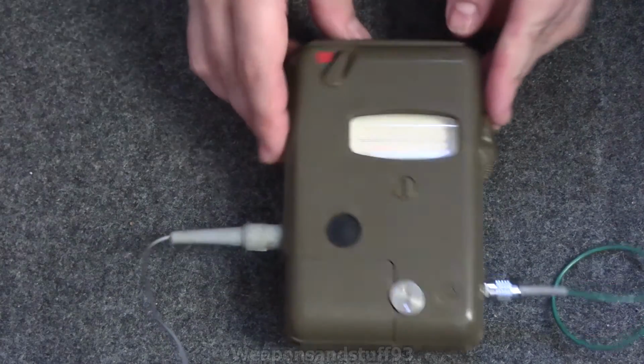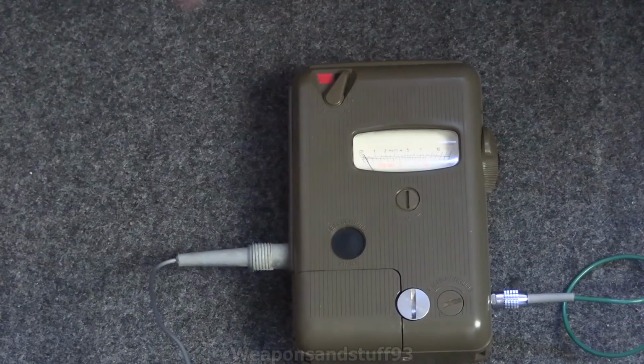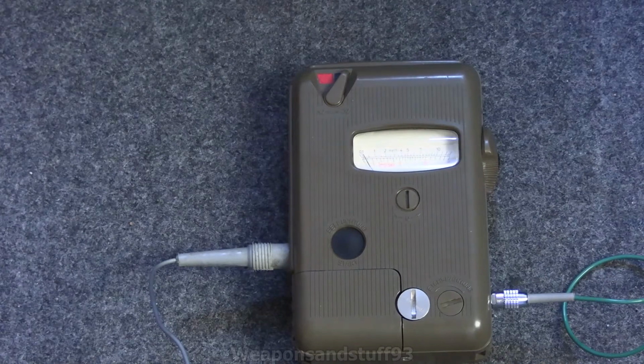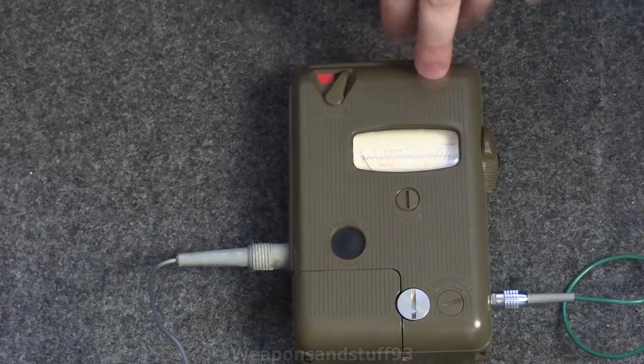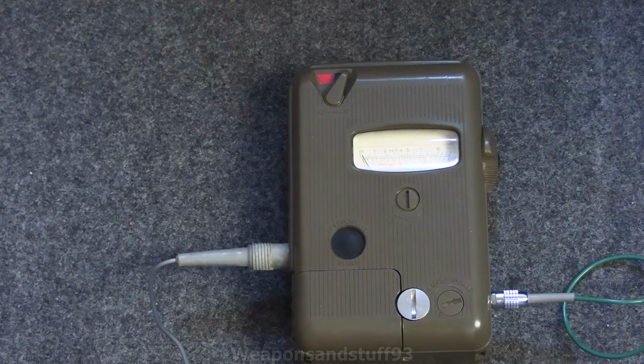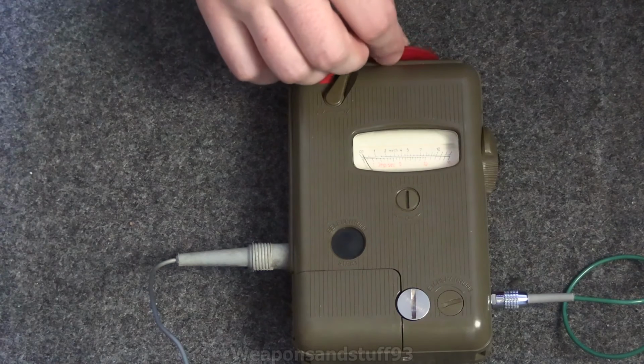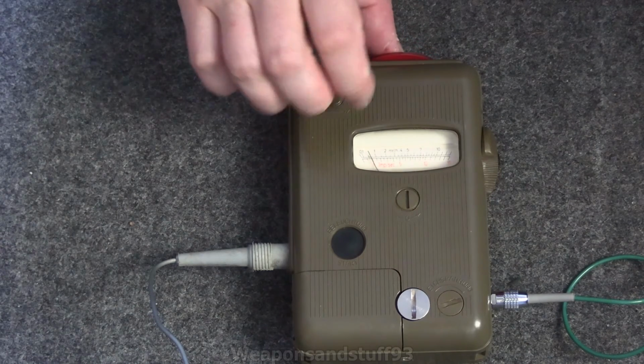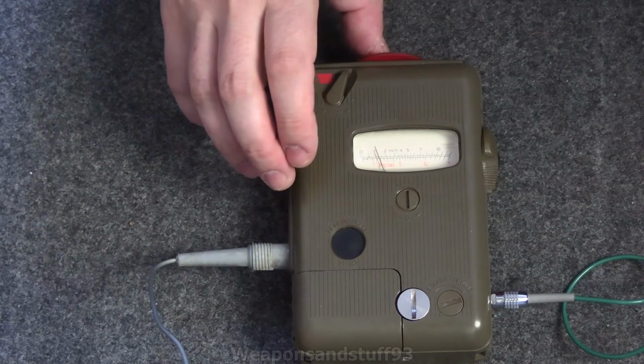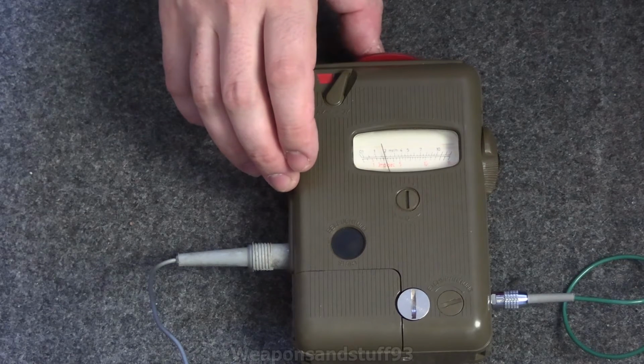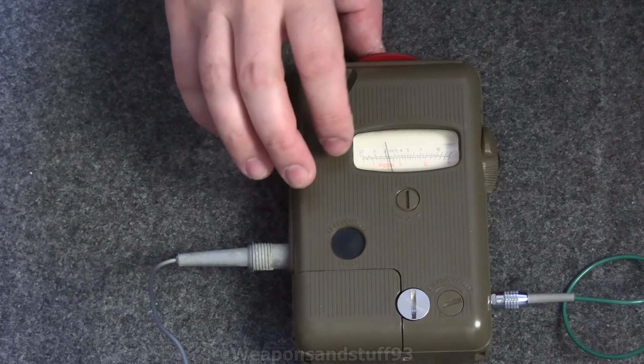Now, the probe is more sensitive, so what I will show you here is, if I open this to be beta and gamma, if I put the little radium sample I've got here to this, it probably won't read much on it, because that's not a very sensitive little window in the top there. Now, it's certainly sensitive enough for my proper radiation sources, but for a little thing like this, you can hear it is picking it up, but the actual little probe is a lot more sensitive as you'd expect. But that's good enough, that little window.